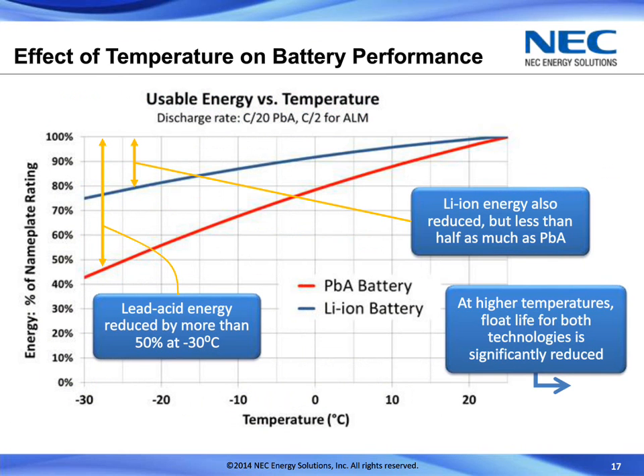So let's take a look at the effect of temperature on battery performance, the other criteria. I'm sorry if this chart's a little bit difficult to read. The red line shows the usable energy or capacity of a lead acid battery at temperatures below room temperature. As we go from room temperature, say 25 degrees Celsius, down to minus 30 Celsius, as might be typical of an outdoor application, the actual usable capacity drops to just north of 40%.